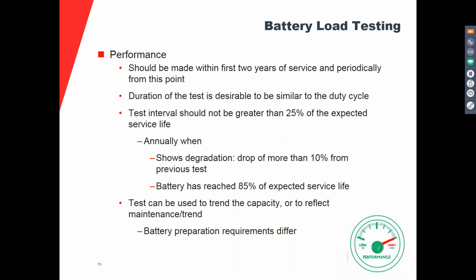Then we have the performance test. This is a test that you do basically as a maintenance test to determine if the battery is holding its capacity and aging as it should be, and is not having accelerated aging. The test should be made within the first 2 years of service, and then it should be performed periodically from this point on. The test interval should not be greater than 25% of the expected service life. We have another slide that depicts this better, but if the battery is expected to last for 20 years, the expectation is to test every 25%, which means every 5 years.